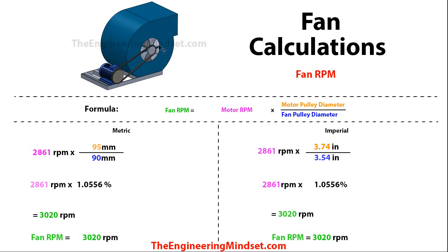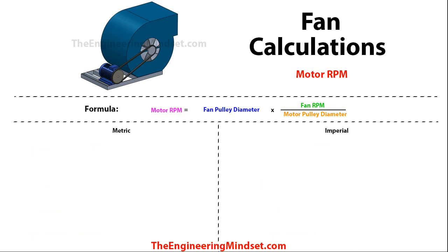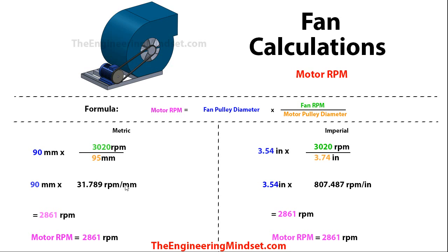We can also calculate the motor RPM using this formula: the motor revolutions per minute equals the fan pulley diameter multiplied by the fan revolutions per minute divided by the motor pulley diameter. Dropping those numbers in, this will come out at 2,861 RPM on both imperial and metric. Again, you can calculate these or look them up from the manufacturers.